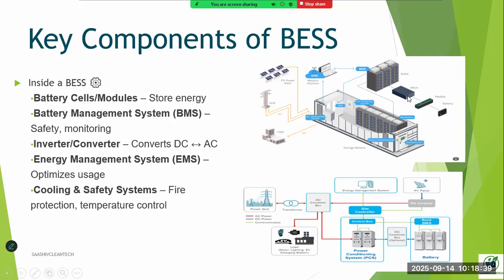Why is it required like this? The reason is, as you know, the battery voltage is around 2.8 to 3.2 volts per cell. When you look at high power in terms of kilowatt and megawatt, we need to have a DC voltage of 1000 volts. To get 1000 volts, we need to group together 300 plus cells of 3.2 volts in series to form 1000 volt DC.